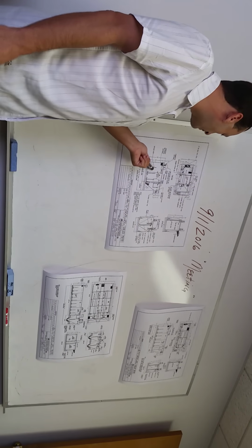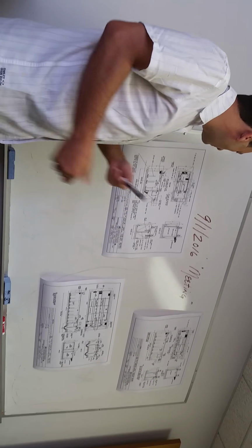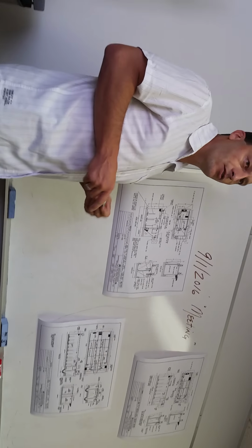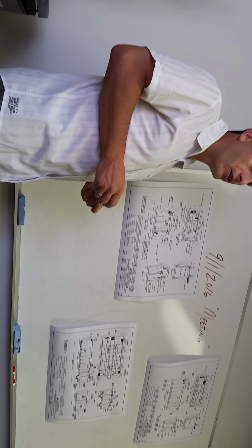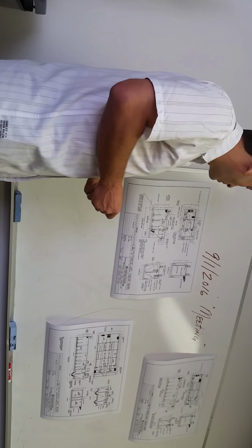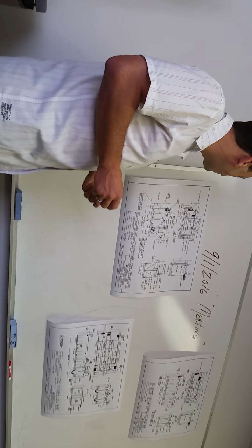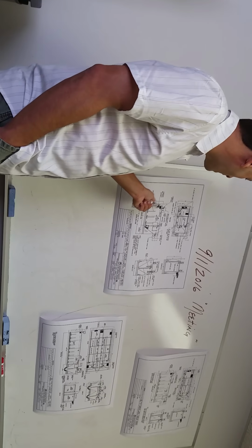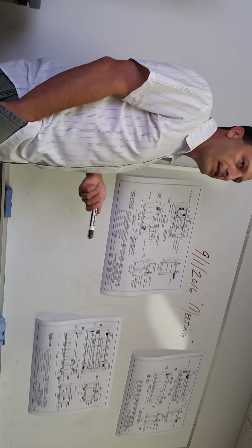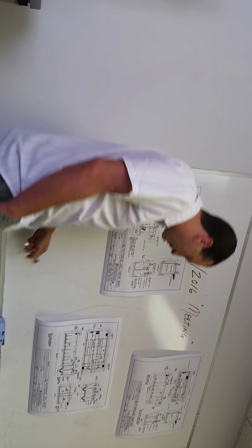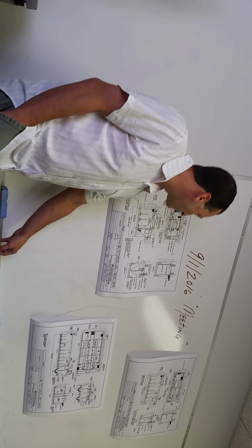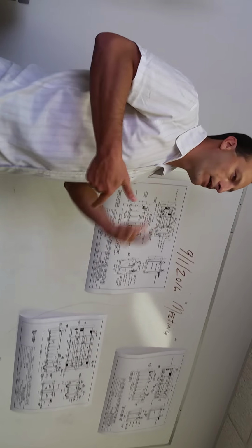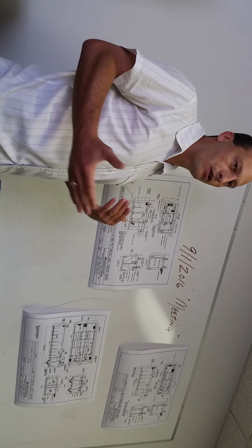We're still looking to keep this as an aerated tank. So if you guys remember from 2 weeks ago, we're maintaining aeration conditions above 0.5 milligrams per liter in there. Typically they're going to run 1.5 to 3, somewhere in that range on average. Though the way that we operate an EA plant is a little different than the way that we operate an SBR system, especially when it comes to our controls, because in an SBR system, we're running the blowers 24 hours a day. One of those blowers is always running.